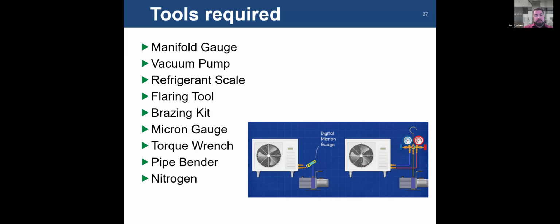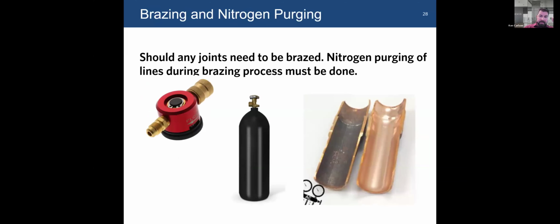You'll need a brazing kit, in case you need to braze anything. You'll need a micron gauge. You should have a torque wrench set, as there are torque values provided for flare fittings. You should have a pipe bender, right, to make bends as opposed to making joints, and you will need nitrogen and a nitrogen regulator. So, a little tidbit on brazing and nitrogen purging.